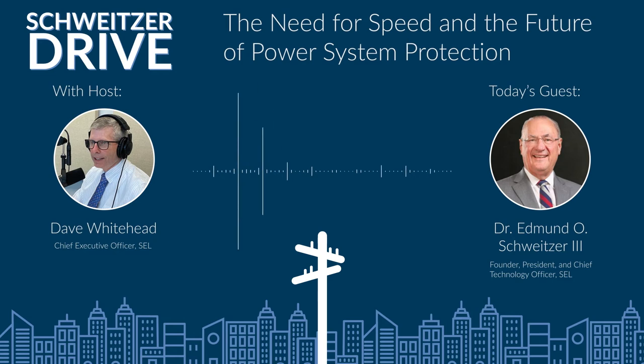So by the time you're down to half a cycle, you're really bumping up against the speed limit for phasor-based protection. In a handful of discussions we've had, we've now hit the speed limit with phasor-based protection. There's just no more we can really squeeze out of our signal processing to detect a fault. And in the follow-on conversations, I've heard you use the phrase, the need for speed. Will you talk a little bit about delivering energy at the speed of light?